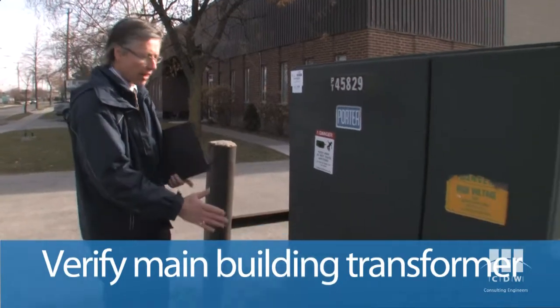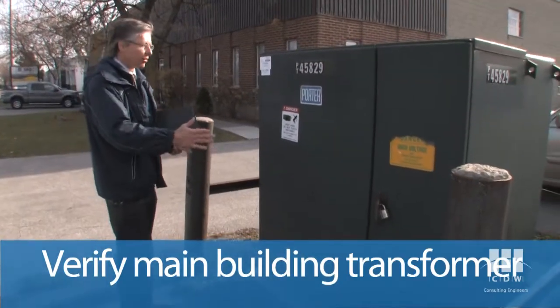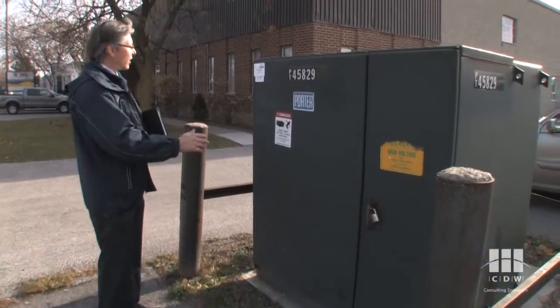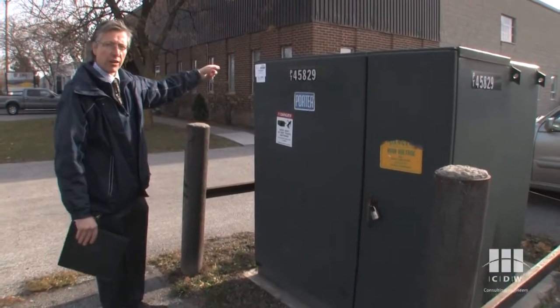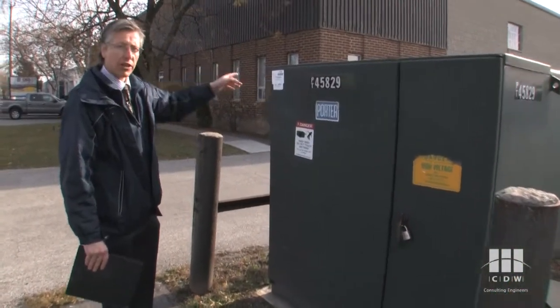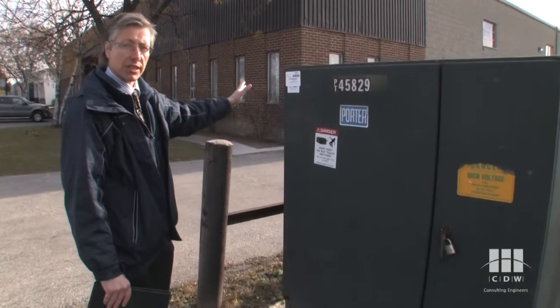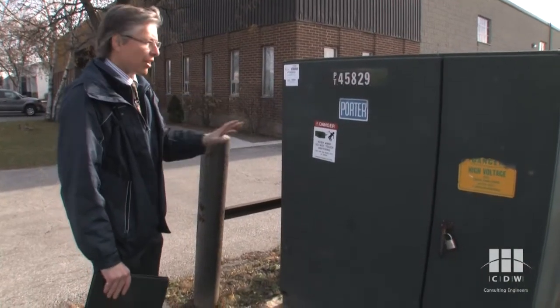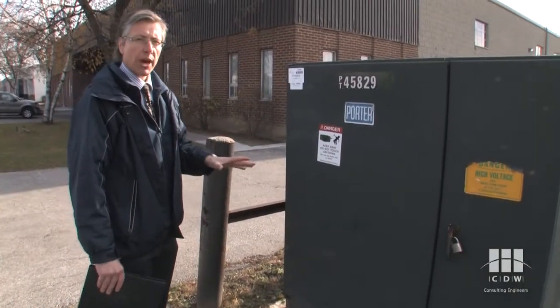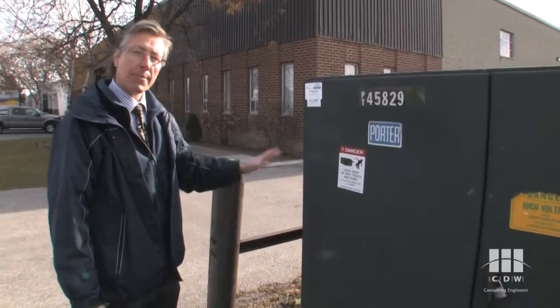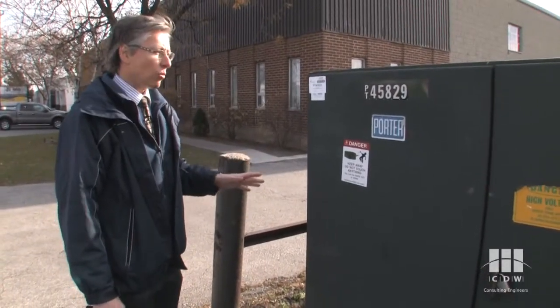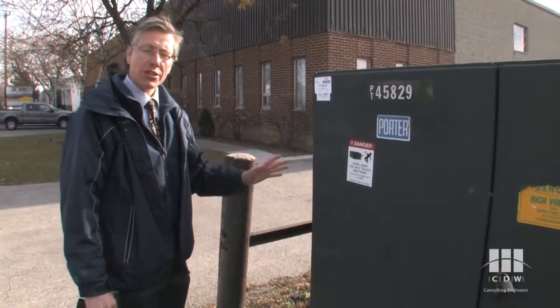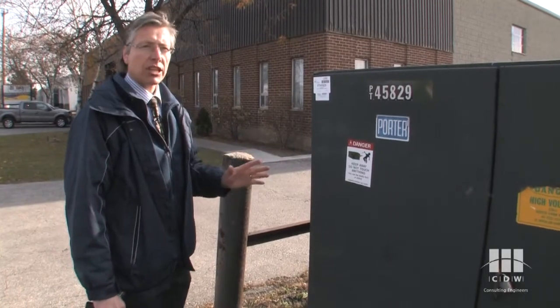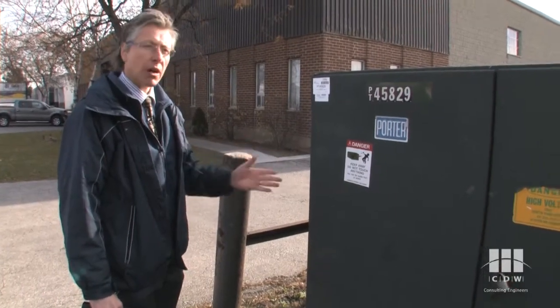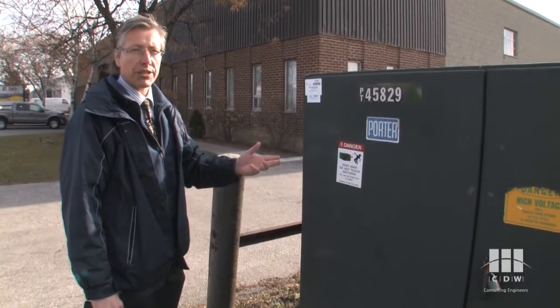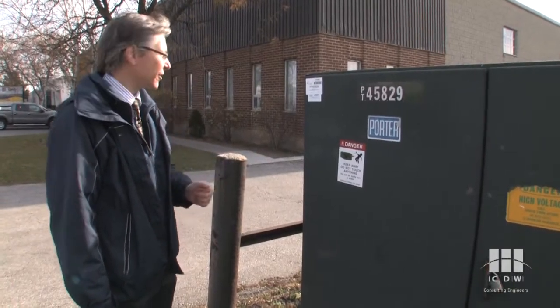In this case, we have a pad mount transformer on the property at the front corner, and the electrical room is just over here, about 30-40 feet away, so I know this transformer feeds this building as well. Very often these transformers are owned by utility providers and not by the building owner. So while we don't own it, we still need to look at it to get an idea of its size, and if there's a problem, it usually gets replaced by the utility provider.